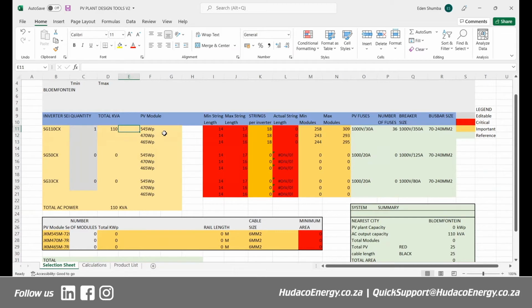And here it already shows you that if you choose a 545 watt peak panel, your recommended range per string is between 14 and 17 panels. The 18 written here is because the inverter has 9 inputs and 9 MPPTs, and each input takes 2 strings.